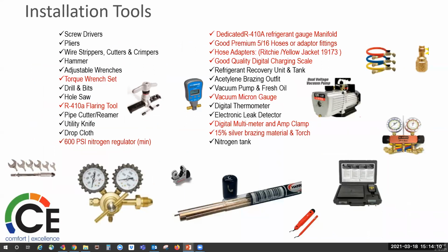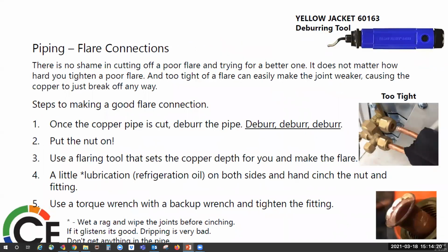Most of you have these, whether they're at your shop, installation van, or truck. A couple things we're going to point out here are a good flaring tool and a good deburring tool, in order to get the burrs off there. A bad burr will make you have a leak, and a nice smooth one gives you less chance of a leak. You can also put refrigerant oil on a nice good flare to help it seat better. You want to use a torque wrench and a backup wrench to make certain you have the proper torque and a good connection, and you can refer to the installation manual for the correct torque settings on these flare nuts.